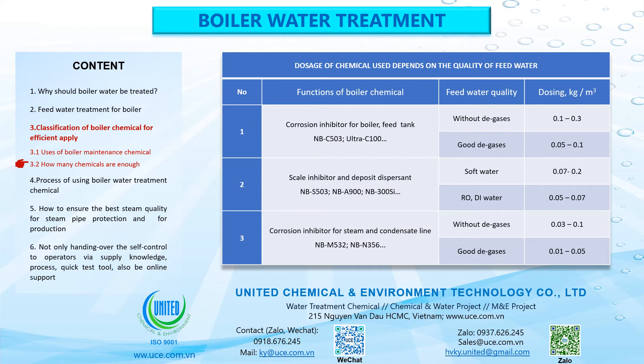The following table shows dosage of chemicals depending on feed water quality. 1. Function: Corrosion inhibitor for boiler feed tank — NBC 503, Ultra C100. Feed water without degassing: dosing 0.1 to 0.3 kg/m³. Feed water with good degassing: dosing 0.05 to 0.1 kg/m³.